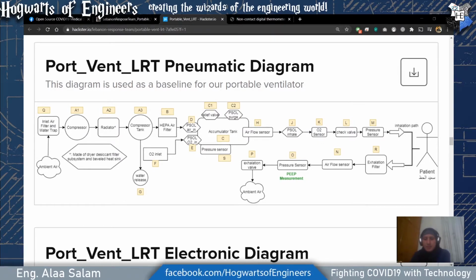So the pressure sensor M is the one that measures how much the ventilator controls it. Yes, it controls. Typically speaking, in the assist control mode, the patient does not breathe on their own, so you are in full control of the breathing cycle. In other modes like synchronous intermittent mandatory ventilation or pressure support, the patient is breathing and the ventilator is observing, and only when necessary it can give a pressure or a breath whenever the patient needs it.